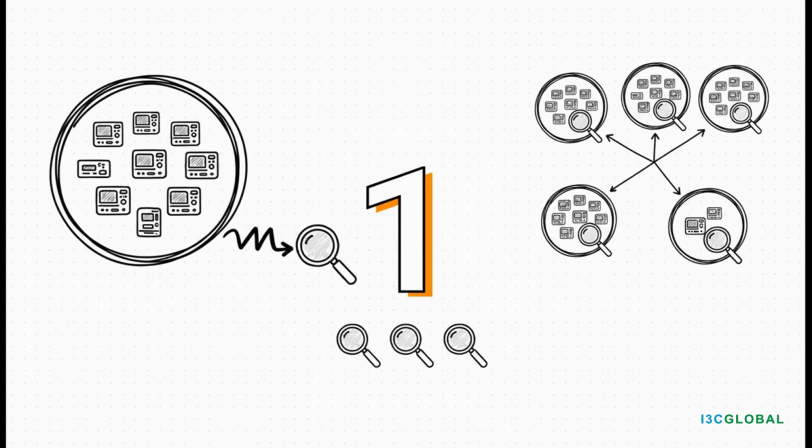And here's the bottom line, the part you really need to hear. For every single one of those generic device groups you create, the notified body has to pick at least one representative device and do a full, deep dive review of its technical documentation. So let's say you have 10 products. If you can group them all into one family, that's one deep review. But if those same 10 products are split across 3 different groups, well, now you're looking at a minimum of 3 full reviews. Your grouping strategy is absolutely critical.